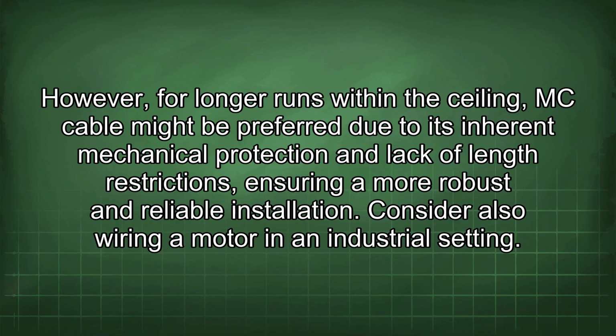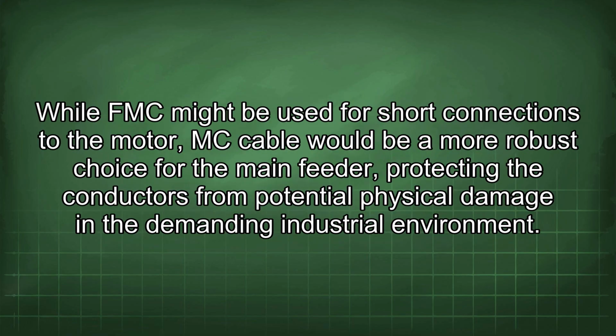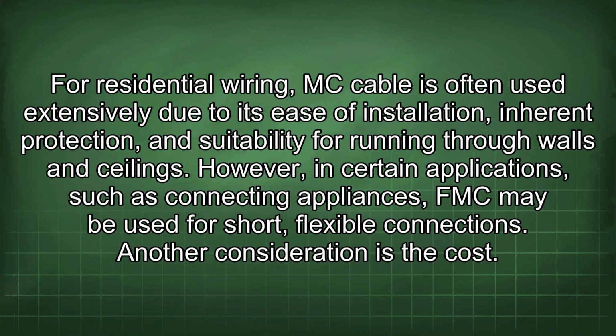Consider also wiring a motor in an industrial setting. While FMC might be used for short connections to the motor, MC cable would be a more robust choice for the main feeder, protecting the conductors from potential physical damage in the demanding industrial environment. For residential wiring, MC cable is often used extensively due to its ease of installation, inherent protection, and suitability for running through walls and ceilings. However, in certain applications, such as connecting appliances, FMC may be used for short, flexible connections.